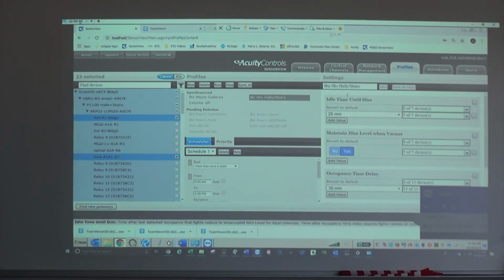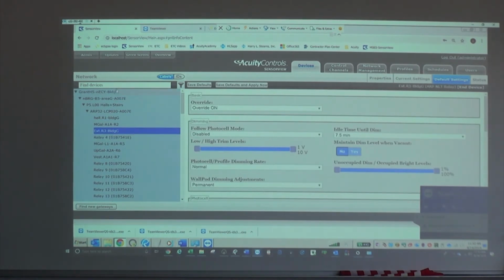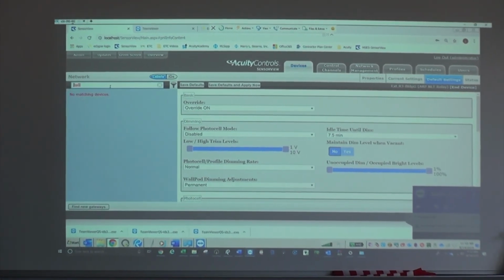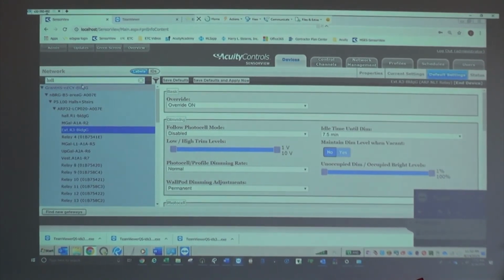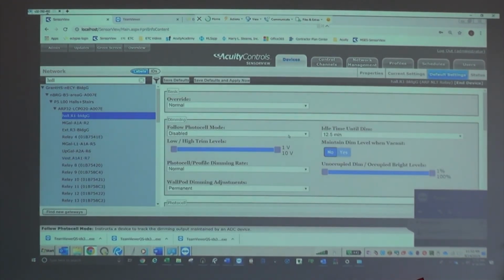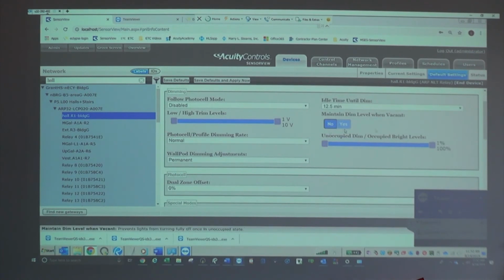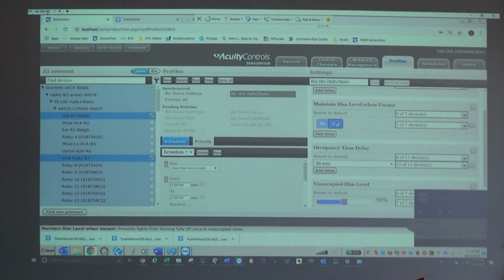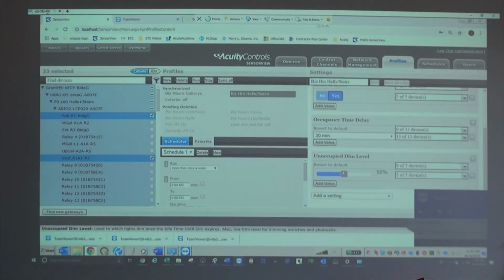Let's look at one of these hallway devices. I'll type in 'hall' since that's the easiest way to find something. There's one right here. The default state of this device has unoccupied dim level at 0 and maintain dim level when vacant is off. But during profiles, you can see maintain is on and unoccupied is at 50.